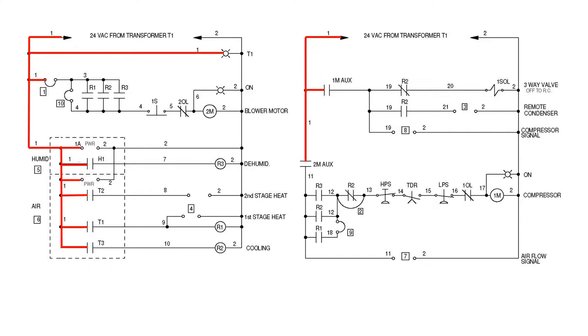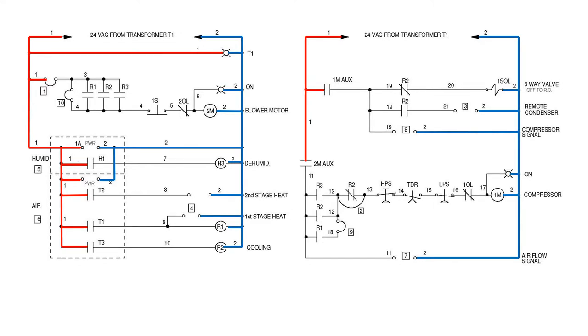The wires labeled number 2, shown in blue, are the transformer common. Note that this example, like many DCA dehumidifiers, requires a jumper wire or some type of normally closed switch to enable completion of the blower circuit.